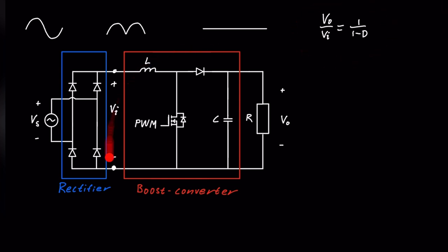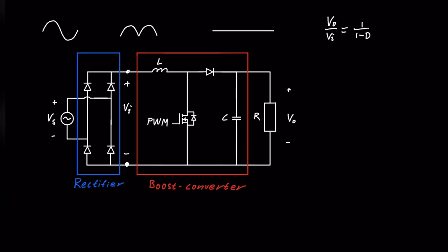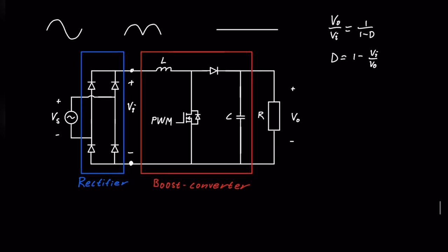This gain holds even though the input voltage isn't a perfect DC. What is different from a regular boost converter is that the duty cycle is not constant. Rearranging the equation gives D equals 1 minus VI over VO. In steady state VO is constant, but VI is not constant — it has a sinusoidal absolute-value waveform. Therefore, the duty cycle would be 1 minus that waveform, which is the opposite waveform.